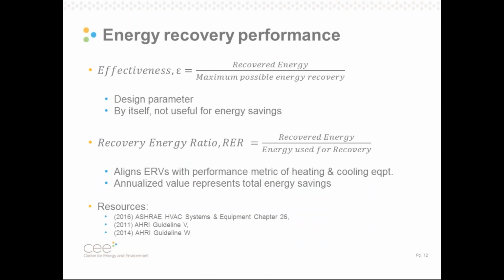Energy recovery performance is mainly defined using two metrics. Usually there's only one metric that enters any discussion, and that is the effectiveness. The effectiveness is a ratio with a maximum value of 1, and it's a ratio between the recovered energy, how much energy this system recovers, compared to the maximum possible energy recovery. And the maximum energy recovery is just a thermodynamic maximum. So in practice, all ERVs will have effectiveness less than 1. In practice, most units today have effectiveness between about 0.6 and 0.8.